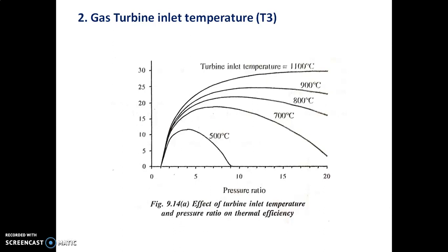Next is gas turbine inlet temperature. The increase in turbine inlet temperature at a given pressure ratio increases the work output from the turbine. At the same time, however, the heat supply in the combustion chamber is also increased. But the rate of increase in turbine work is greater than the rate of increase in heat added.